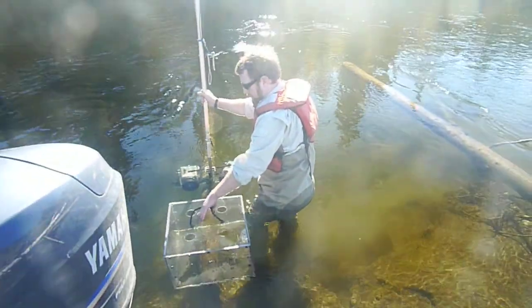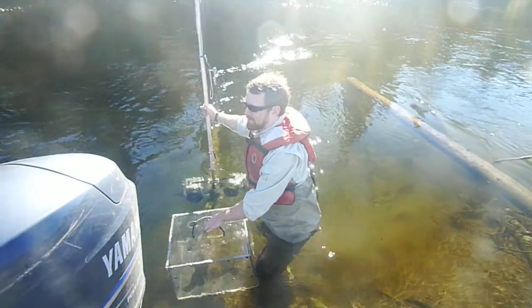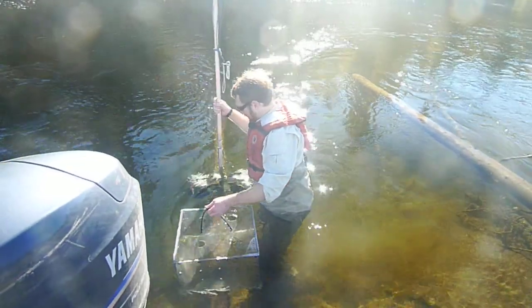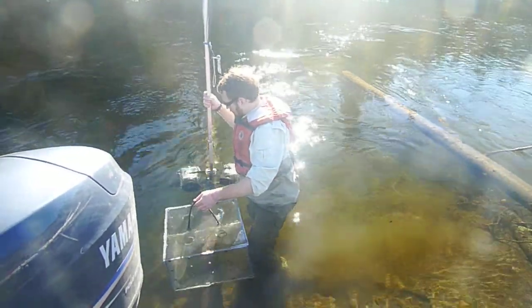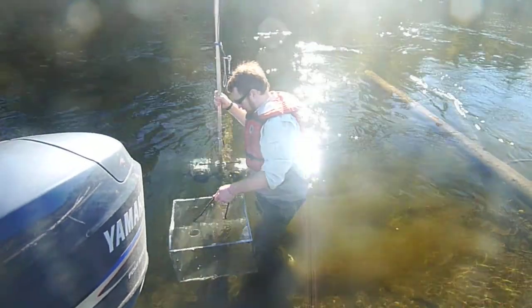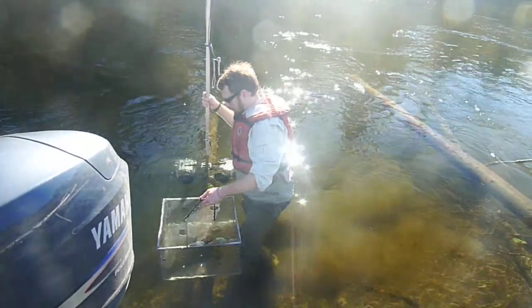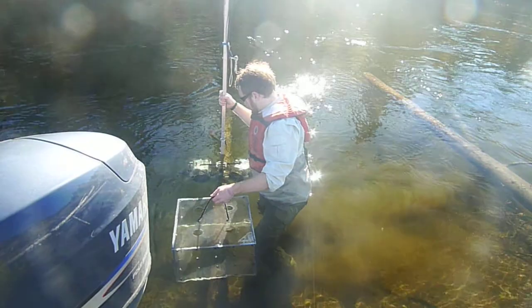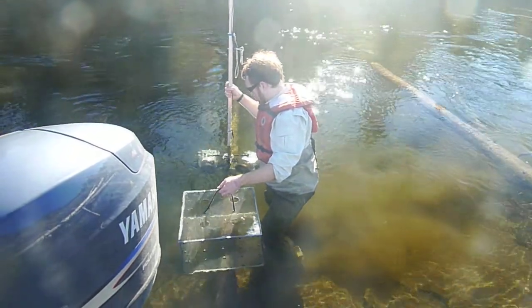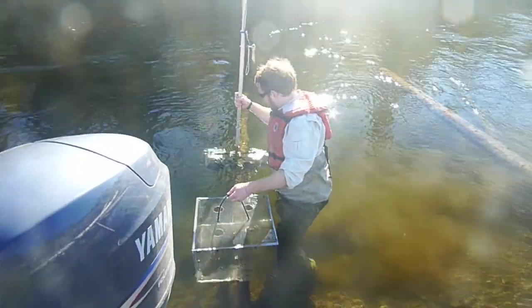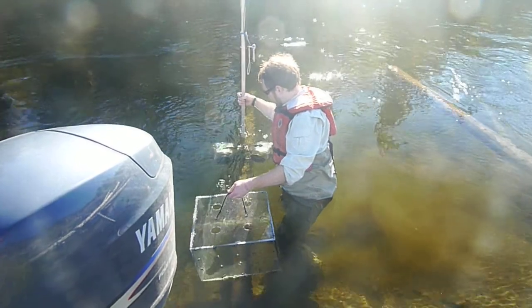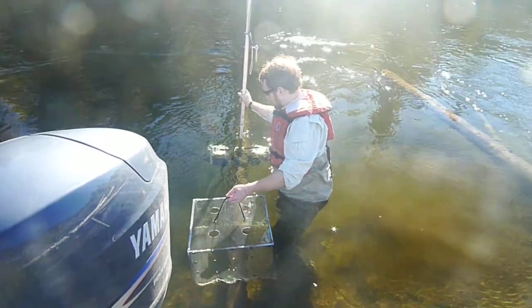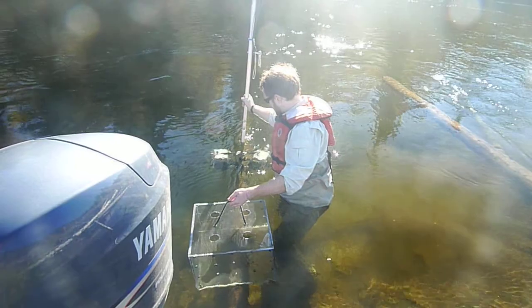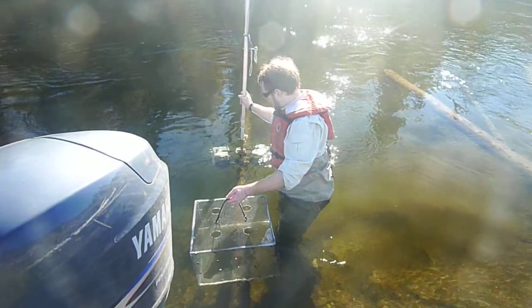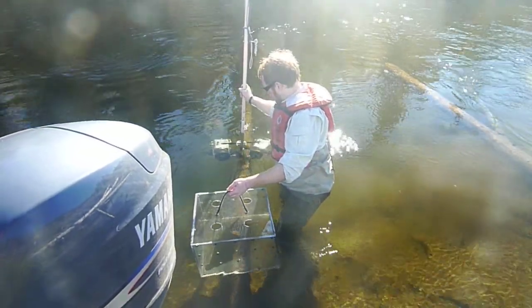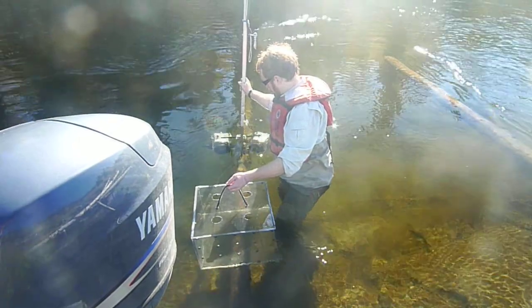You have those kinds of errors every time something moves around when you're measuring it too. So all the moving fish and everything have those tiny errors, and that's one of the main sources of the small error in those measurements. The important thing for keeping it still during the calibration, though, is that an error in the calibration is going to affect not just the one measurement, but all of them. And there's no reason that these things have to be moving. So just be careful to keep them really still.